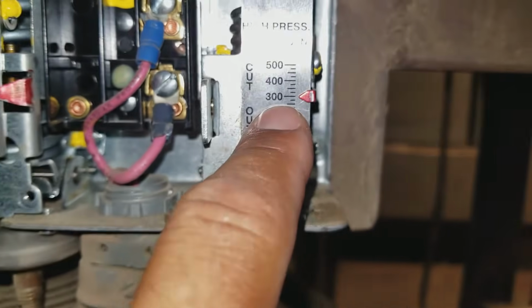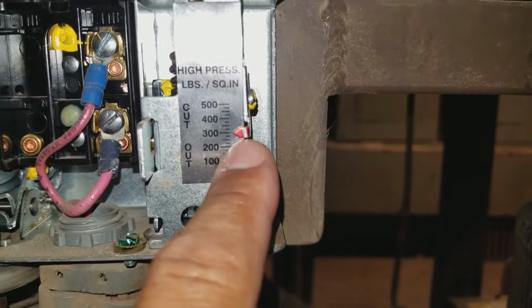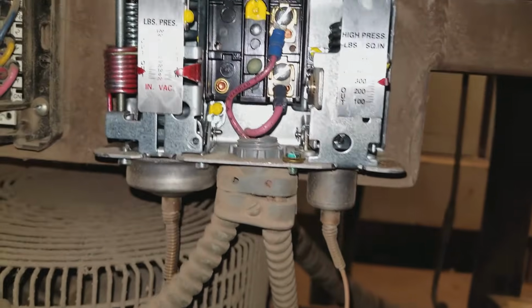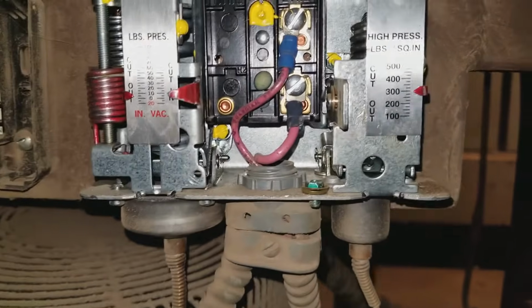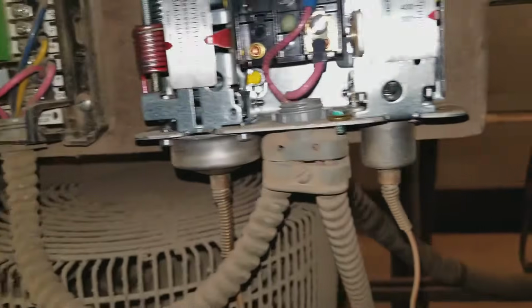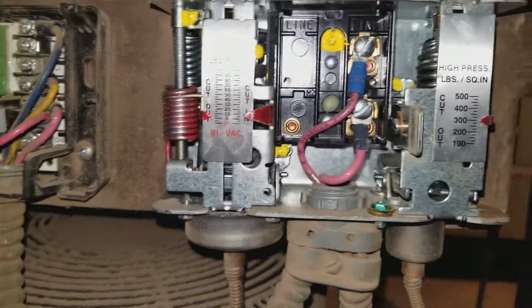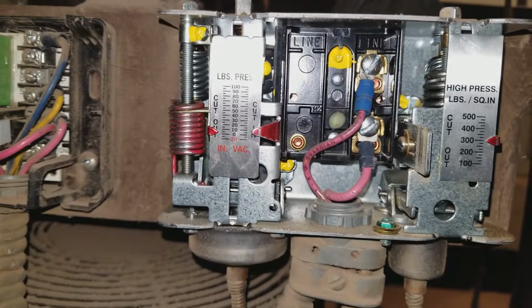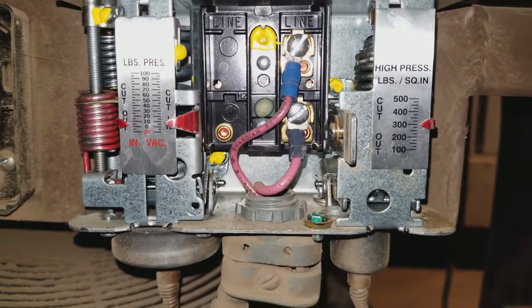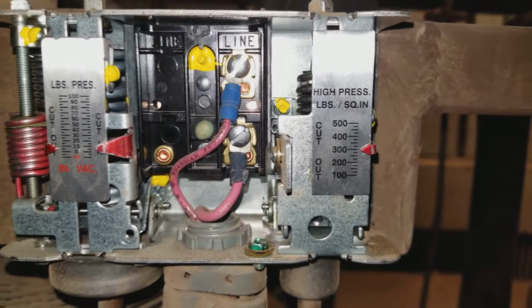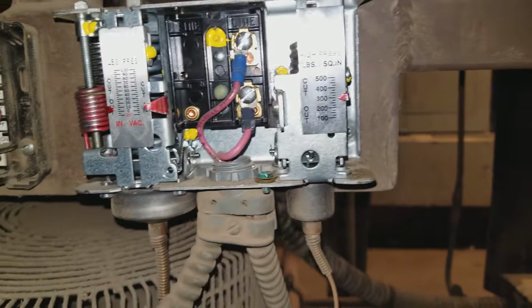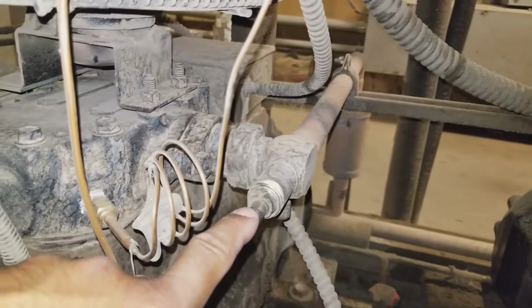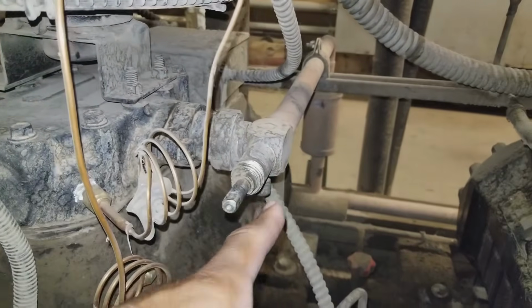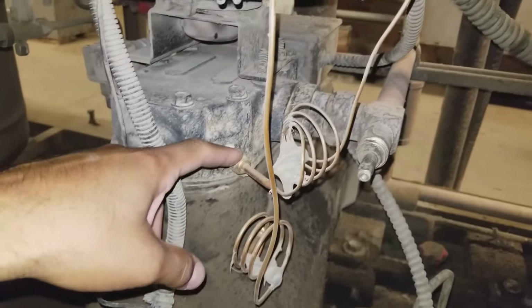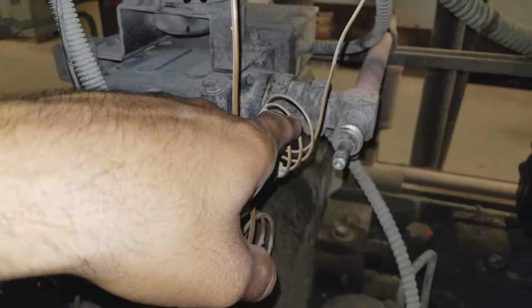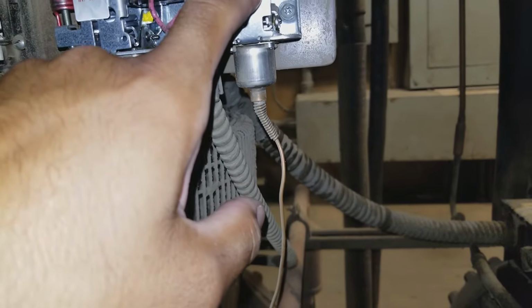Right now it says it's at 300, but you never want to trust the needle. That could always be off. So when they originally installed it, they adjusted it for 300. And if you look at R22 on your PT chart, which is on my phone, about 125 degrees to 130 degrees Fahrenheit, if you convert that over to R22 pressure, that comes close to 300. So according to this, it's within range. So to check the proper way, we're going to put a high pressure gauge on my discharge line, and front seat this all the way in, to see how high I can get my head pressure and see if it terminates early or not.